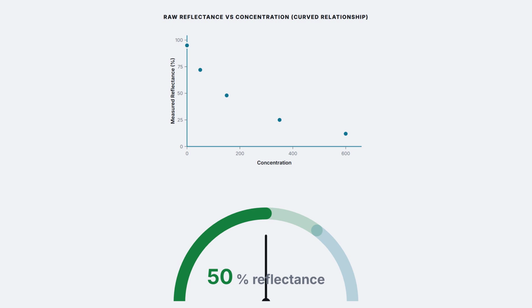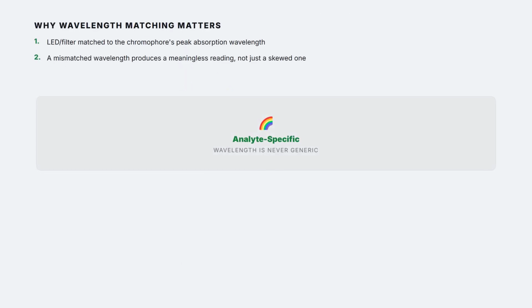Wavelength selection matters as precisely here as anywhere in spectrophotometry. The reading LED or filter is matched to the specific chromophore's peak absorption wavelength for that analyte's chemistry, and using the wrong wavelength, a mismatched slide type loaded with the wrong reagent card, for instance, produces a reading that's simply meaningless, not just slightly off.